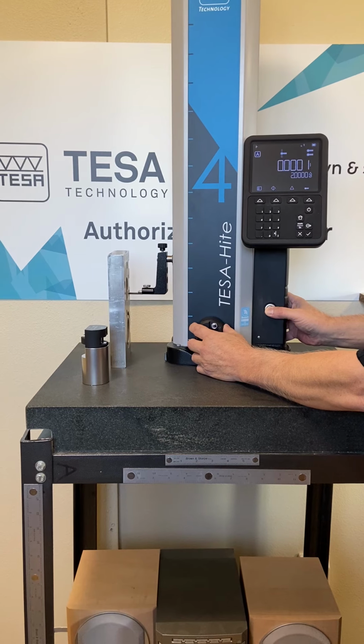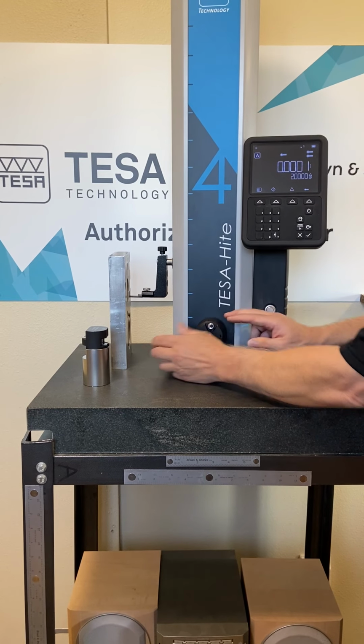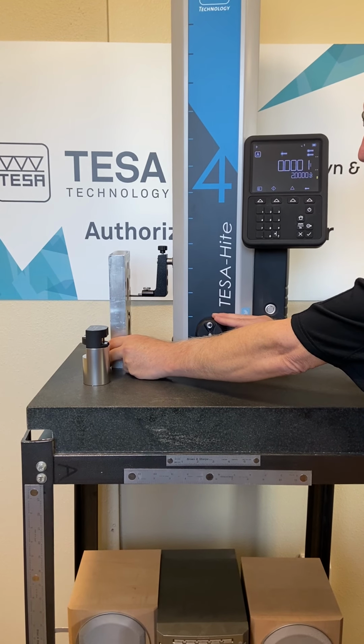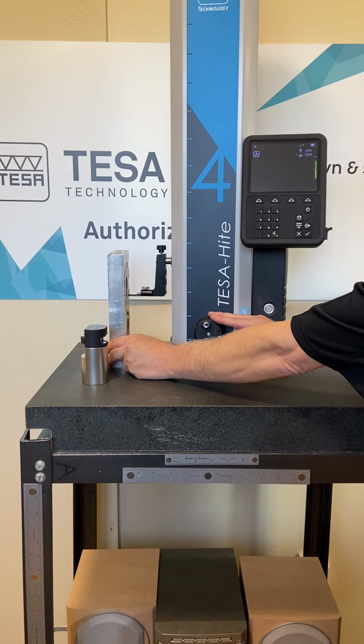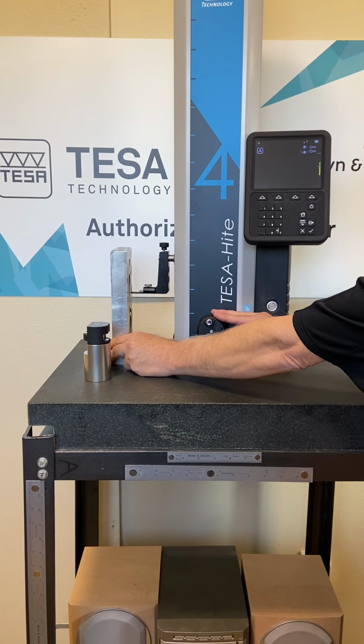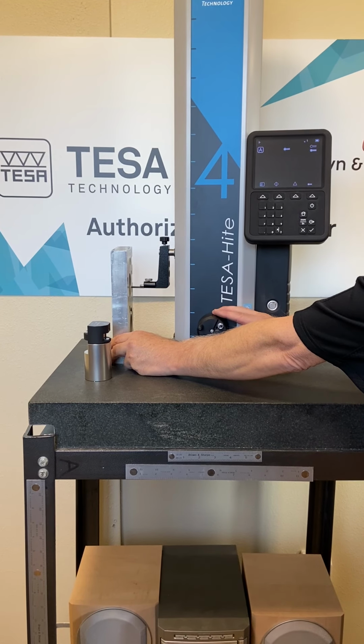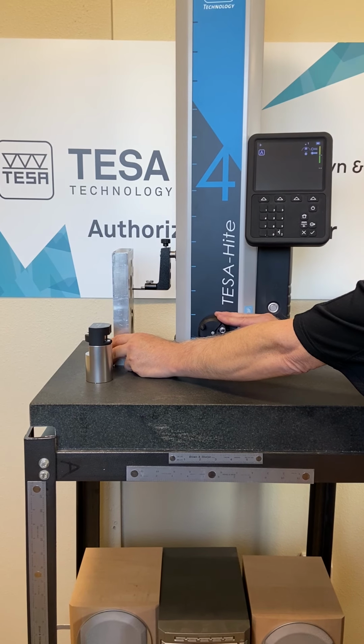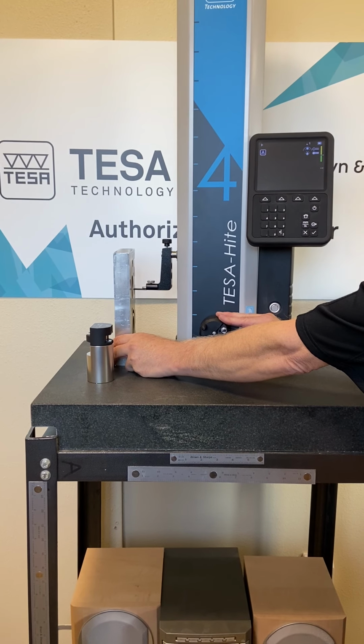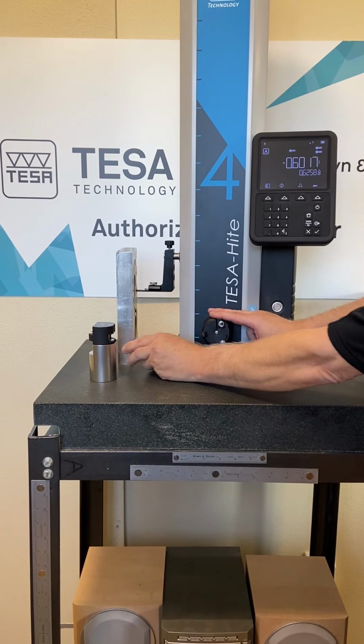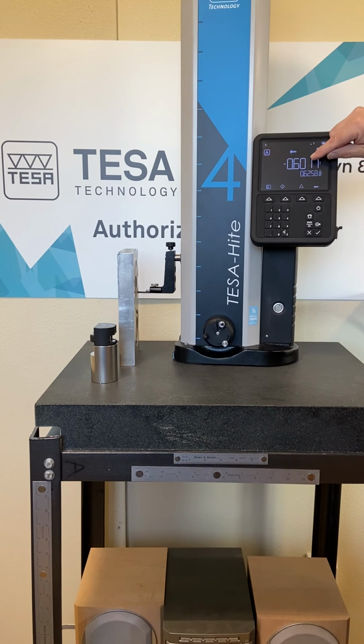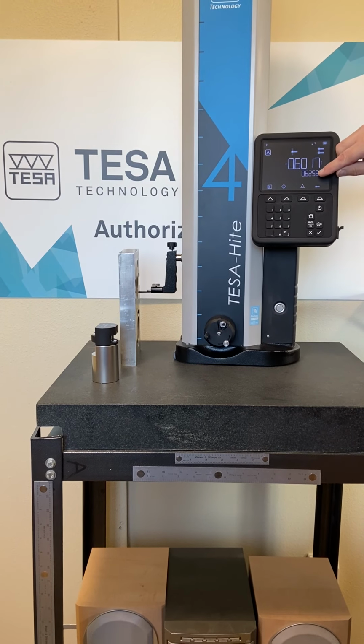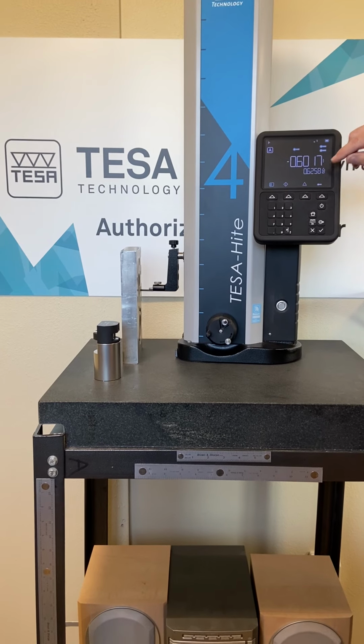Again, diameters, you just want to be up on the bore just a little bit. You come down here and take a measurement. I'm holding pressure on it. I sweep the part. I go to the top. The green lights are in between the 2 lines. I sweep the part across. And again, there's my center line measurements in reference to the big bore, and there's my diameter.